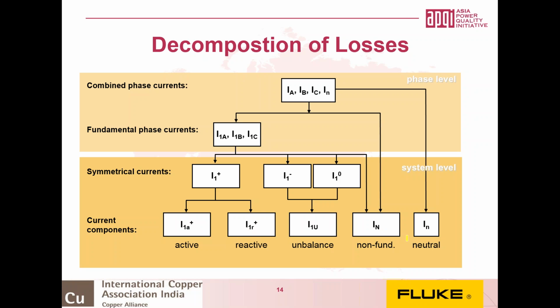Again, we're excluding the neutral current, which is processed separately, so it comes directly from the phase level. Once we've determined what the IL is, then we can calculate the various losses from the physical phenomenon. The line loss due to the active current is unavoidable, and they can only change that by having thicker conductors, which typically is not economically feasible unless you're really close to the limit on it.